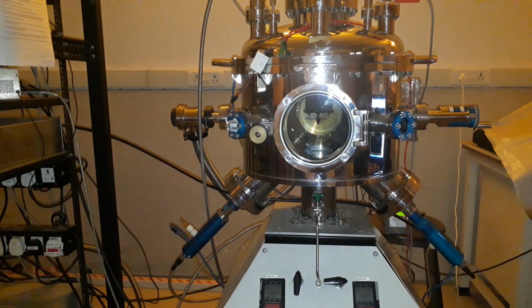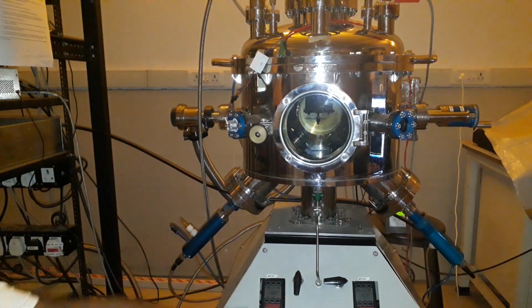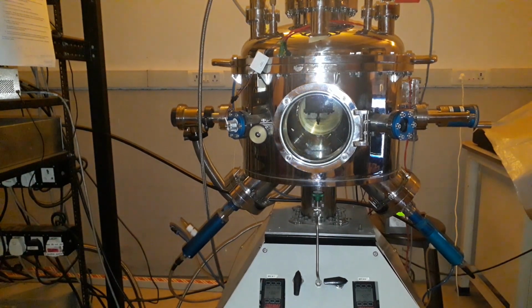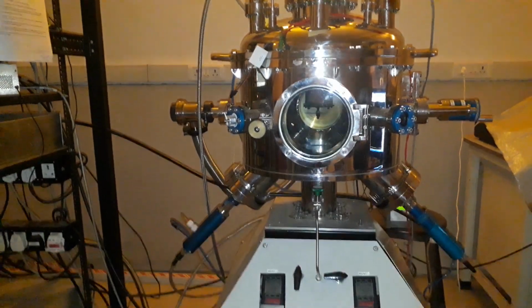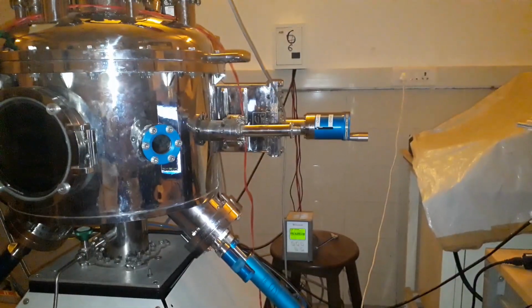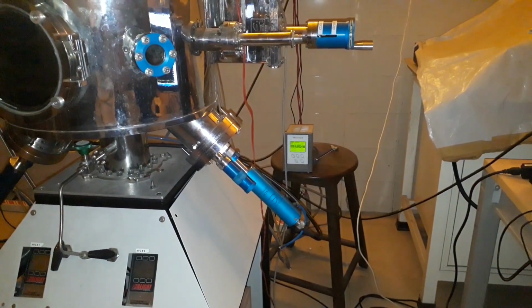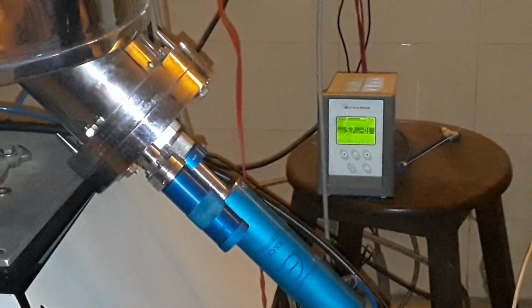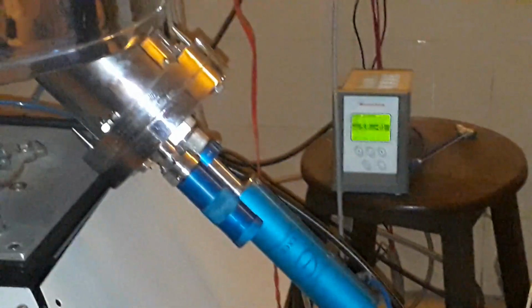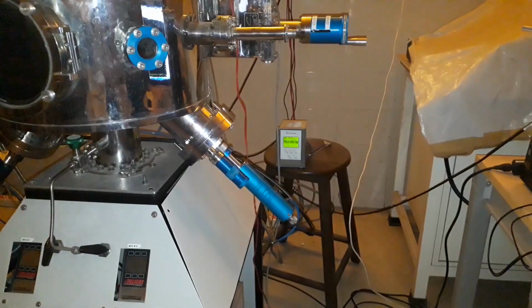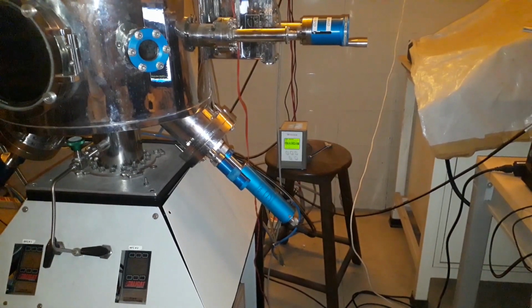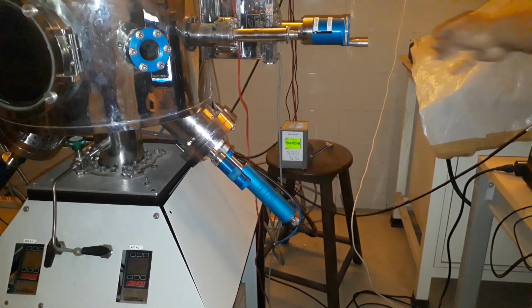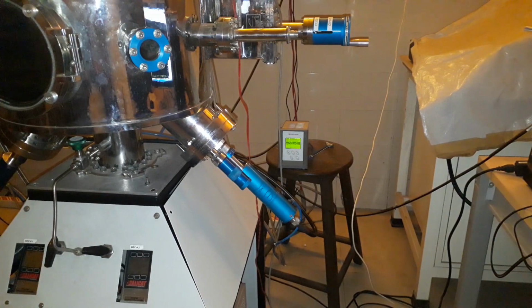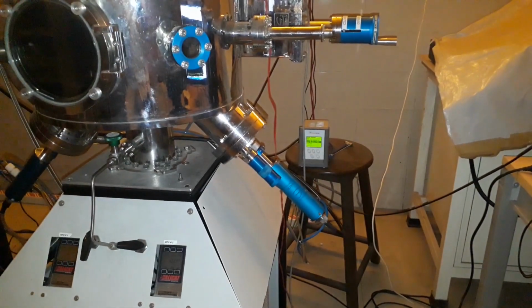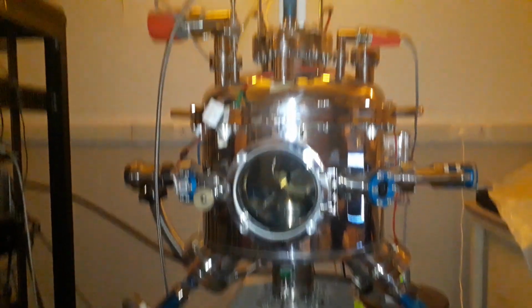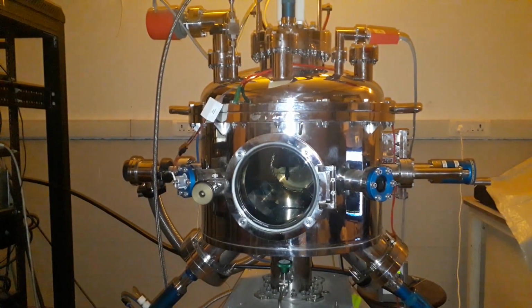So right now it is set at 30 SCCM, temperature is 23 degrees, and I have put the turbo on standby mode. If you see there, on the meter, the pressure is 5.7 minus 1 millibar. Sorry, it is standby mode. I have closed the gate valve as much as possible to control the pressure. Otherwise, it's too much load on the turbo pump, which is not good. So everything is set nice and fine.